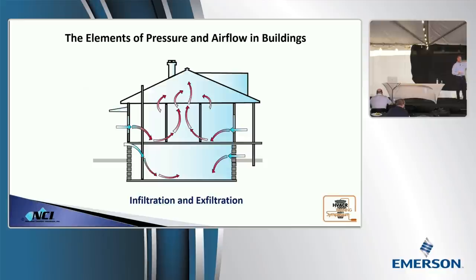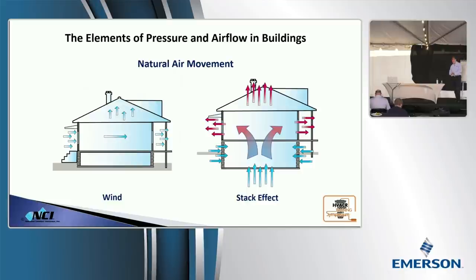So we either have air coming in or going out. This is always happening. Remember rule number two. If you got 1 CFM going out, you got 1 CFM coming in from someplace else to replace it. And sometimes it's coming from places that we don't want it to. So as we look at this, there has to be a driving force. As we said earlier, buildings are sandwiches of material. There has to be a driving force. So as we look at these, there are some things to consider. Wind is the first. It's the unknown variable that you can't account for. As we talked yesterday, you're going to see air moving in and out of this building, and you can liken that to combustion air. It's changing drastically. Now, if we have fuel-fired equipment in this building, we're wide open to the outdoors. You're not going to run out of combustion air, right?